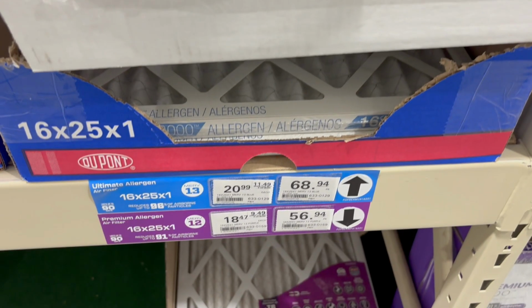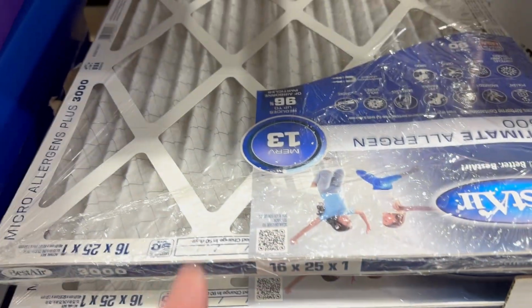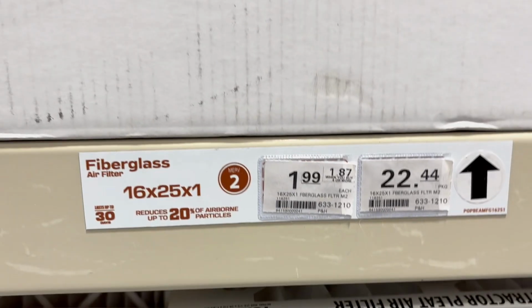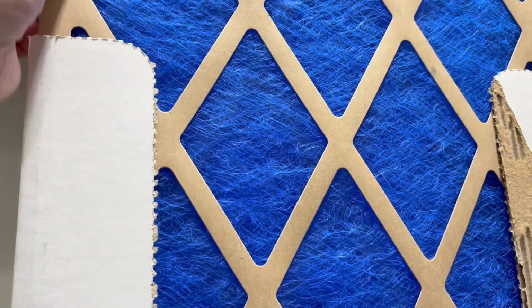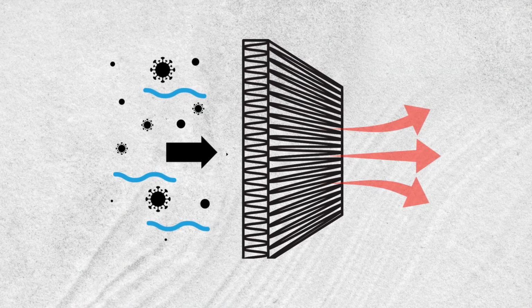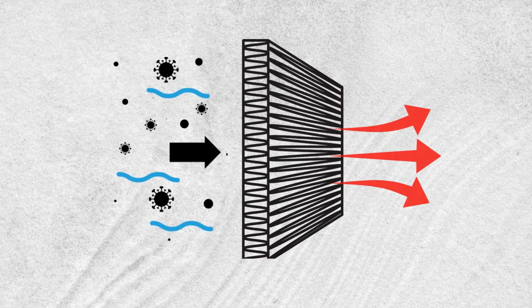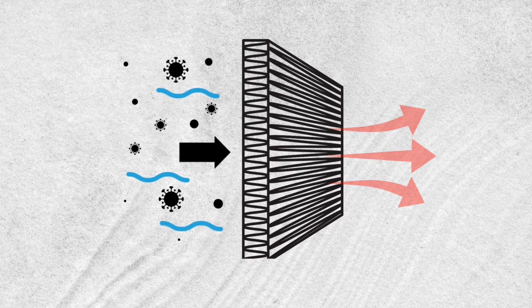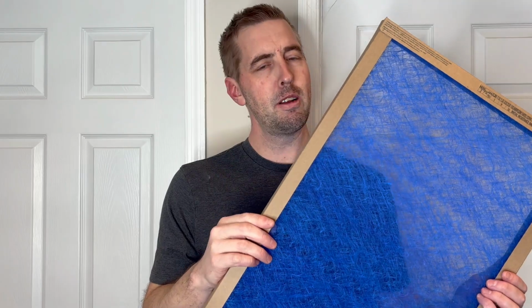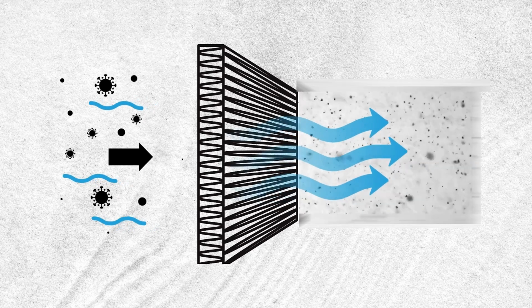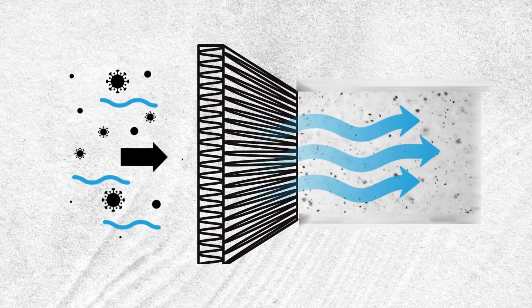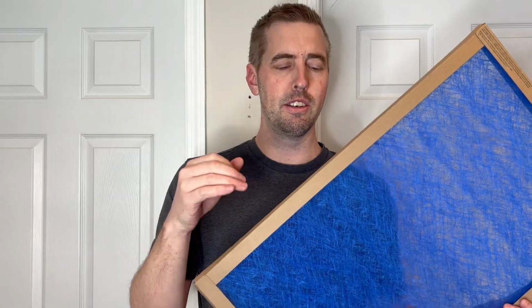As we stroll through the filter aisle in the store, it's easy to assume by looking at the prices that the more expensive filters must be better for our HVAC systems and our homes. However, in many cases, the more expensive filters can actually restrict airflow, which can ultimately do more harm than good when it comes to performance of the system. And lower MERV filters are generally going to be cheaper than the higher MERV filters. They're going to allow more dust and particulate to pass through, but they're also going to allow more airflow. And that airflow is key because that's what's going to get you more efficiency in your heating and cooling. That's going to reduce the amount of strain on the blower motor. And overall, it'll just allow for better temperature control and comfort in the house.